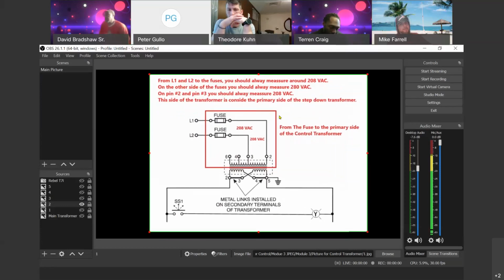From L1 and L2 to the fuse, you should always read around 208. On the other side of the fuse, you should always measure 208, guys, not 280. I made a mistake, a typo. It should be 208 on the other side of the fuse. Pin 2 and 3, we talked about this, drill it in your head. We should still be reading 208. This side of the transformer is considered what? Primary side. And the step down transformer, okay?